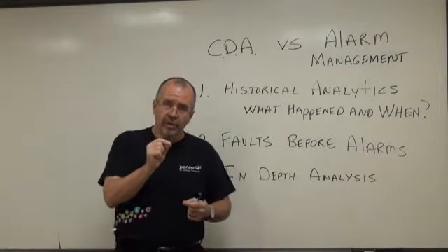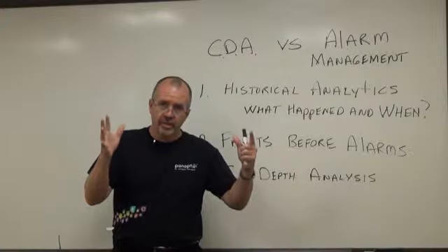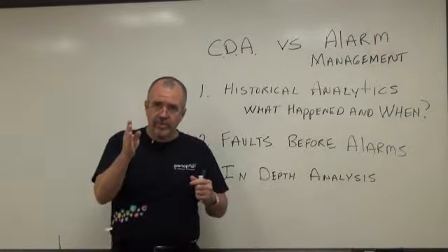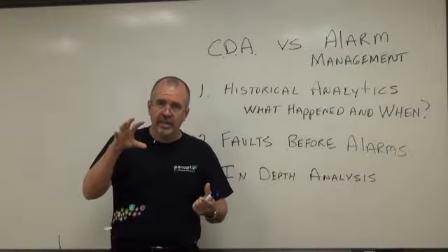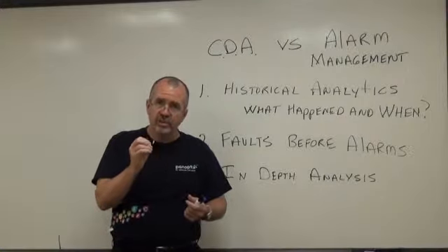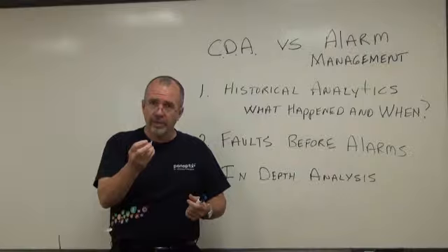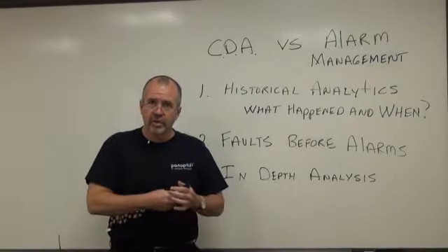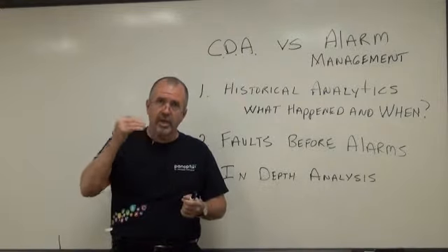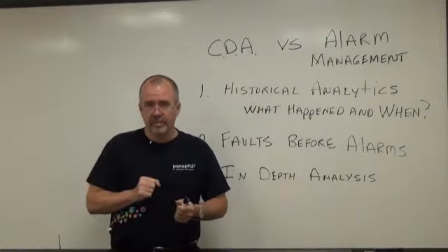When you click on a fault within CDA, you immediately jump into Custom Analyzer showing when the faults occurred, the time period the fault lasted, and all of the data that was used to feed information into the fault analytics. Quickly, an example: if you had a temperature fault for a VAV box, you are taking a look at the occupancy of the VAV box, the temperature in the zone, and the zone set point, all tracked for you, presented as soon as you click on the fault.